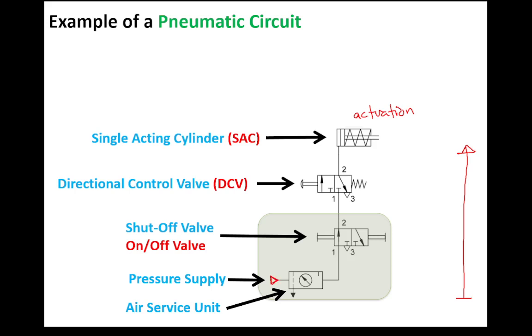This symbol represents air supply or pressure supply, which comes from the compressor. And this air is loaded with particles, dust and moisture, which needs to be filtered out and then regulated in terms of pressure and then lubricated if necessary. That's why this component is called FRL, which is filter, regulator, lubricator.